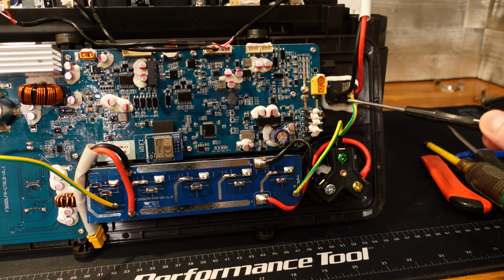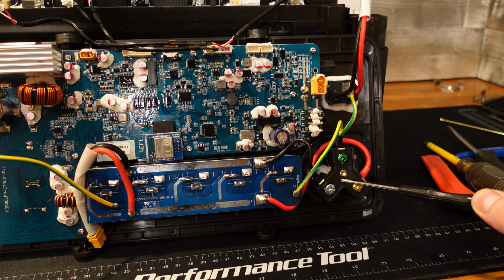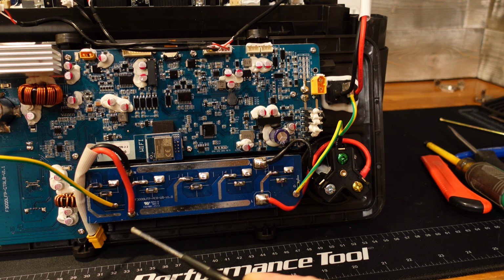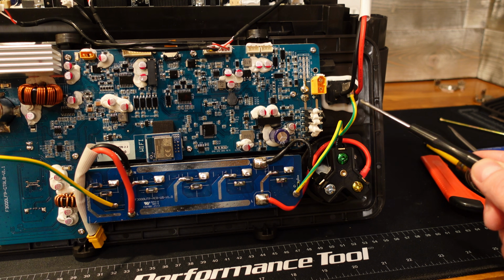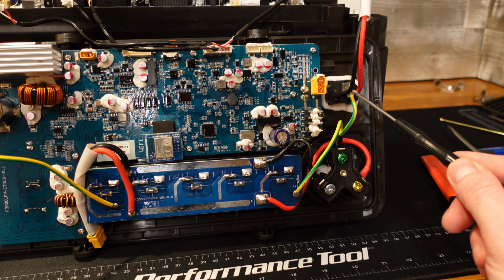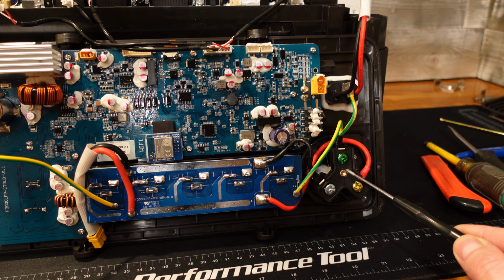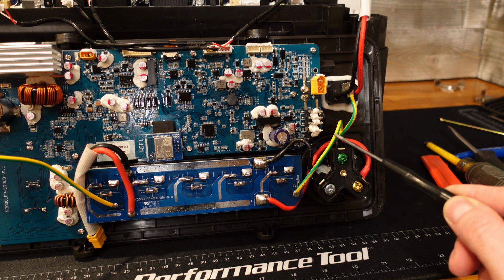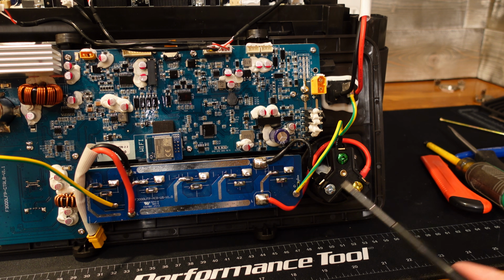We have our AC input here on the right, our 30 amp output receptacle, and our 20 amp receptacles on the bottom. The grounds are all bonded together, so we have the input ground, then the output 30 amp directly to the output 20 amp receptacles. Again, all bonded together. That's perfect, that's what we want to see.